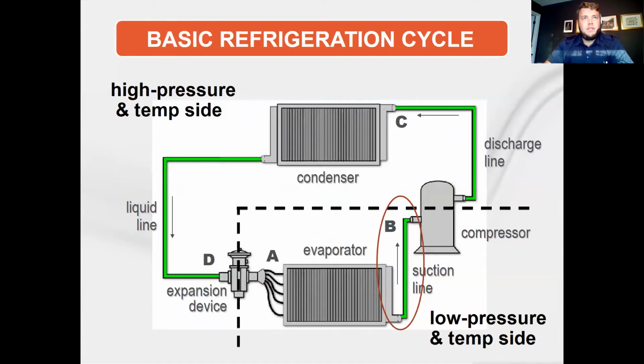So nowadays we're using R410A. We used to use R22. We'll discuss a little bit of that later, but the heat that is absorbed evaporates the refrigerant within the coil and moves over to the suction line. The suction line is in its gaseous form, superheated vapor to make sure it's a gas as it enters your compressor. And then the compressor compresses the gas, big surprise, to a higher pressure into the discharge line.